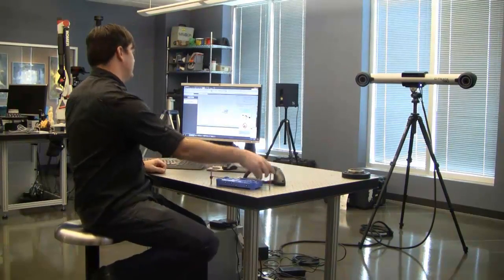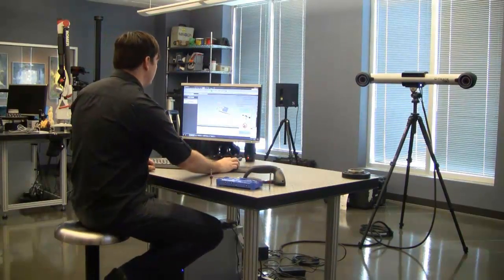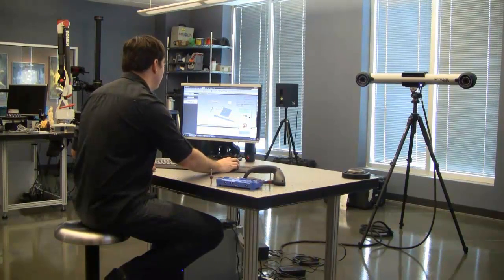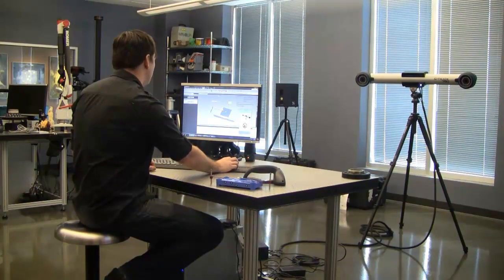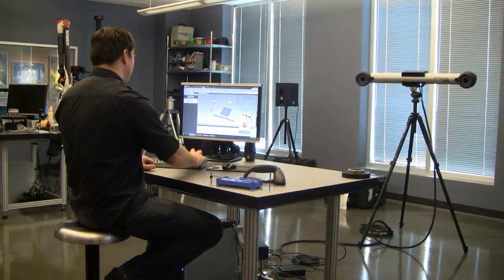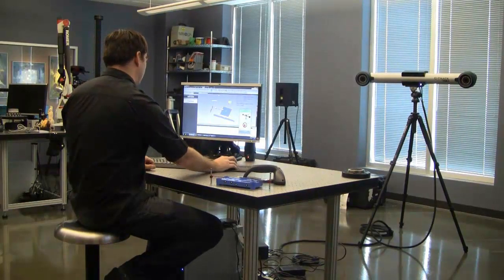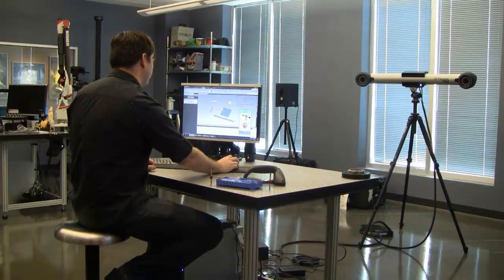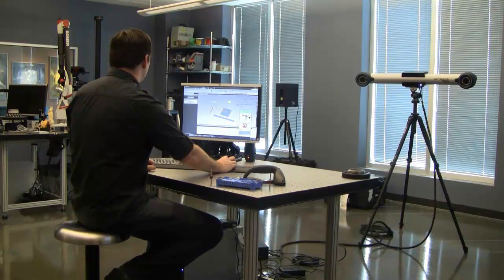So you can see here on screen that it automatically created a distance measurement between those circles, and you see that it was 1.9642. If I want to, I can go ahead and type in a tolerance. So I'm going to go ahead and put 2 as my nominal. So that is a measure features between two circles. So I'm going to hit OK.